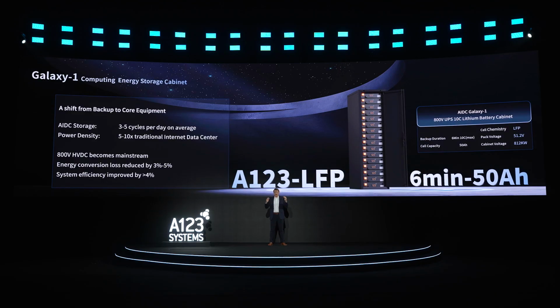Let's take a look at our A123 Galaxy system family. Galaxy 1 is our AI data center cabinet, 800 volt DC architecture, equipped with 12 to 24 kilowatt hour per rack, reducing conversion losses and boosting system efficiency by more than 4%. Maximum system power reaches 812 kilowatt.